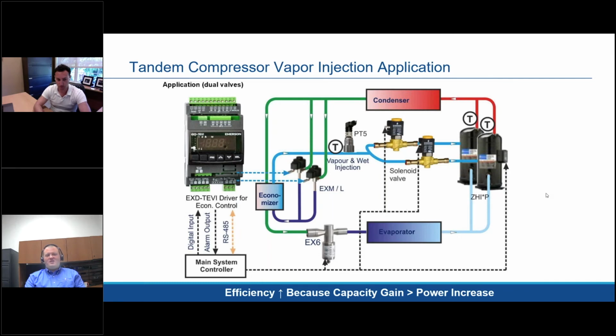So as you can see, it's a little bit more complicated system than what you typically would see in your standard DX type of system. But these lines are relatively small. They're not moving the same mass flow that you're moving around the entire system. But the size of those lines obviously depends on the size of the system and compressors itself as well.